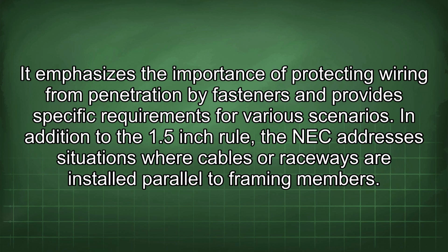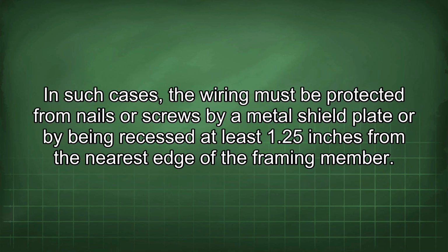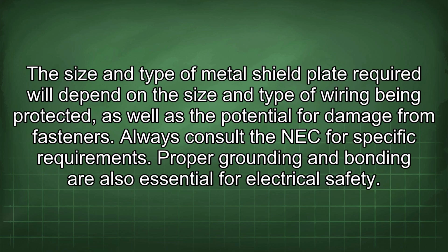In addition to the 1.5-inch rule, the NEC addresses situations where cables or raceways are installed parallel to framing members. In such cases, the wiring must be protected from nails or screws by a metal shield plate, or by being recessed at least 1.25 inches from the nearest edge of the framing member. The size and type of metal shield plate required will depend on the size and type of wiring being protected, as well as the potential for damage from fasteners. Always consult the NEC for specific requirements.